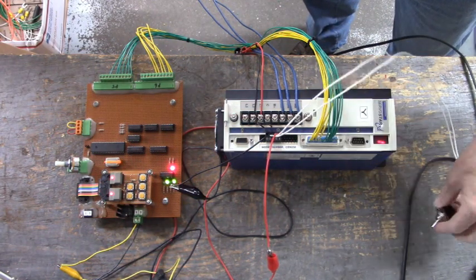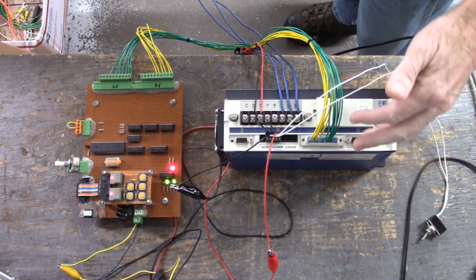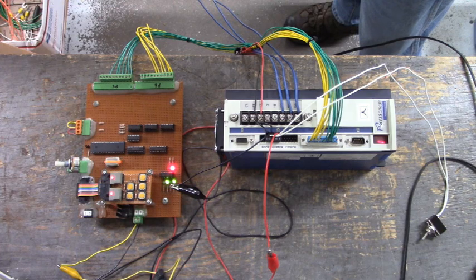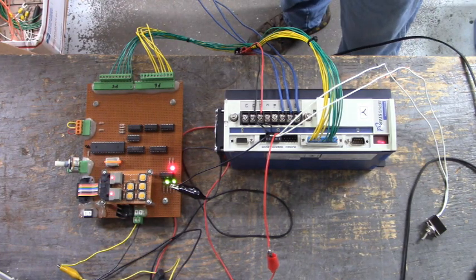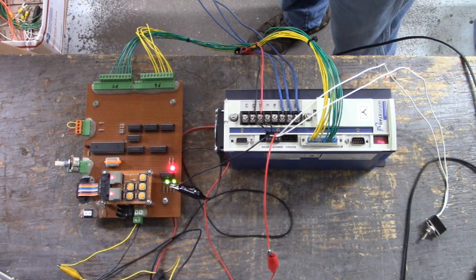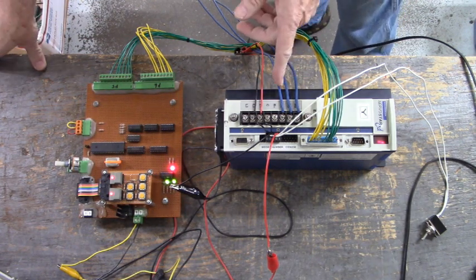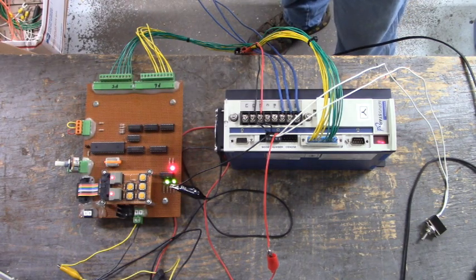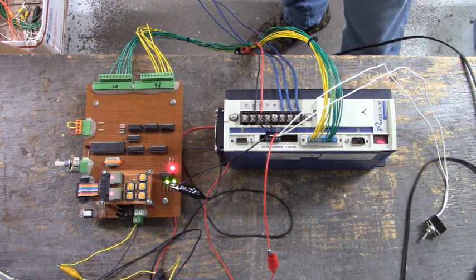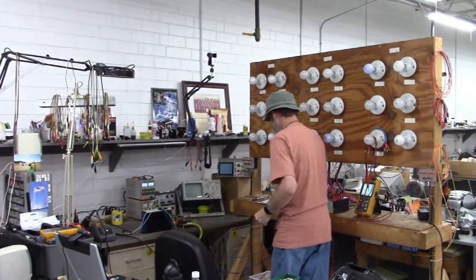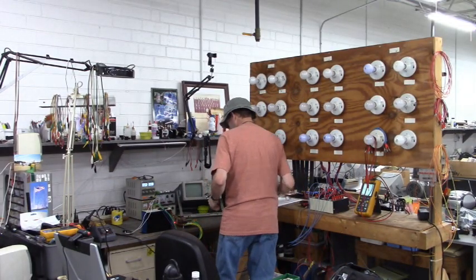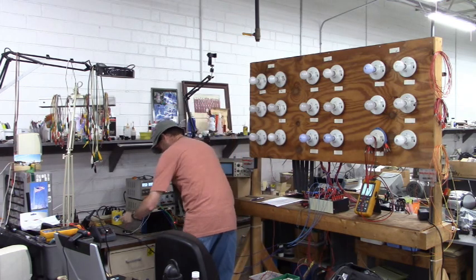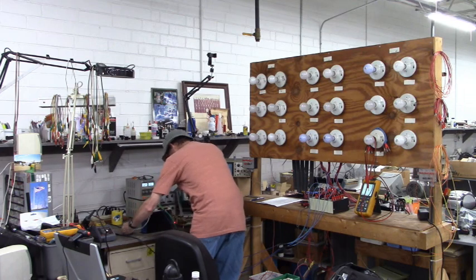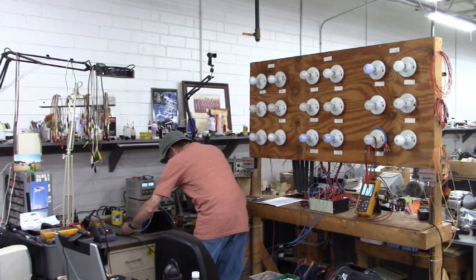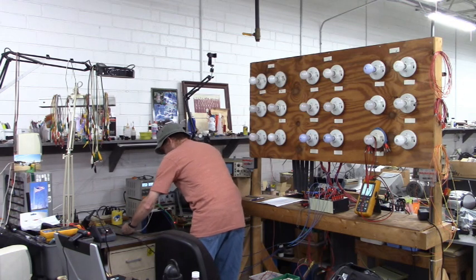Turn that output off. Now what we're going to do, I'll back the camera up so you can see the light bulb sequence that simulates the servo motor when I enable this drive to run. And then we'll look at the outputs of MA, MB, and MC with the Fluke oscilloscope. Give me a little bit to move that camera. Closing C3, pin 8, back to the 24-volt DC ground.